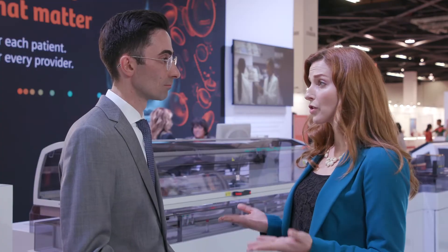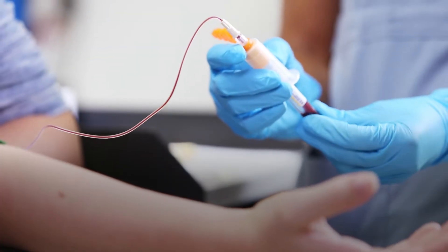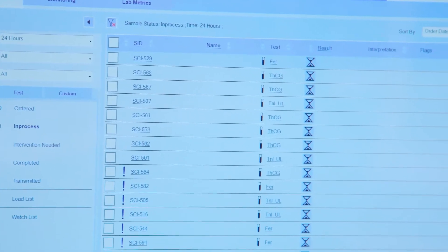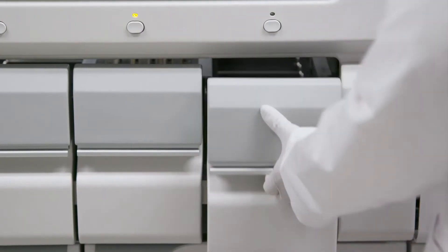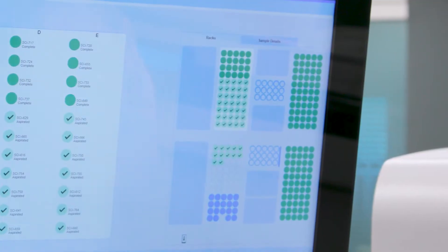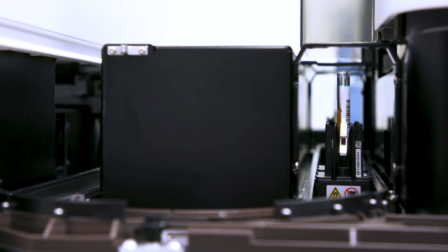Time is saved and errors are reduced. Exactly. And what's interesting is that in the background, the systems are intelligently monitoring the process to predict potential bottlenecks that could impact the process. For example, if an emergency sample turnaround time is being delayed, the system can proactively notify the operator so they can take action. Or if an analyzer's onboard reagent lot number is about to expire during the middle of the run, the system can proactively notify the operator to resolve those bottlenecks before they actually happen.